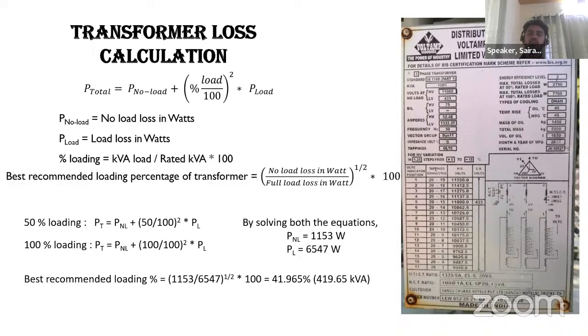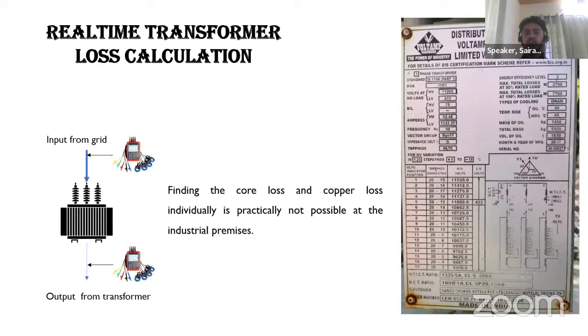For real-time transformer loss calculation at the site, we can't figure out the core loss and copper loss individually, because at the industries it is not possible for them to shut down production and give us time to find the core loss. So what we do is connect two power analyzers of the same accuracy, one at the input of the transformer and one at the output. Then we log the energy consumption of the transformer. We take the difference and divide it by the input energy so that we can find the real-time transformer losses.